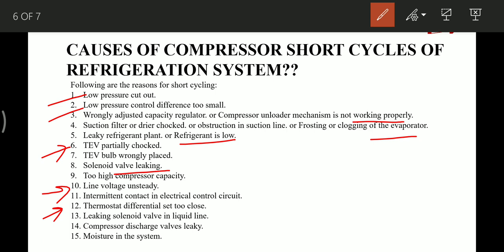Compressor discharge valve leaking can also lead to short cycling. Then moisture in the system can affect and cause choking of the thermal expansion valve. This moisture can also react with the lube oil and create sludge that can also choke the thermal expansion valve. So moisture in the system can also lead to short cycling.